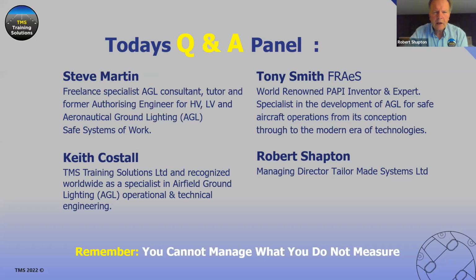Thank you, Keith. Nick has followed this up with a question saying, with regards to AGL isolation, what would be the minimum recommended value, as well as the lowest below which the CCR may not be switched on? I don't really understand the question fully. I think, Keith, what he's asking is, you talked about when you were testing the circuit with faults, various insulation resistance values. It's an interesting question, and it's one that's being debated by the IEC committee at the moment, trying to come up with a standard value.